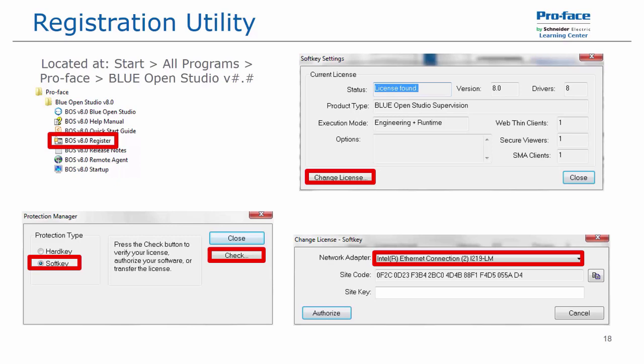One of the primary is the MAC address of the selected network adapter. By disabling the network adapter, it no longer sees the MAC address, and then that site code becomes invalid. Your license is now missing. By simply re-enabling the Ethernet controller or network adapter, your license will return. However, this can sometimes be an issue, especially with wireless Ethernet controllers.